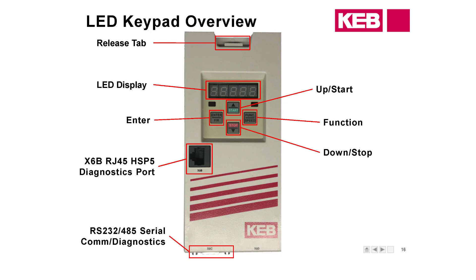The keypad screen itself has an LED display — that's where your parameter name and parameter number are going to show up. We have Enter, Start, Stop, and Function buttons for viewing and changing parameters, and then the release tab at the top. The release tab must always snap up in order for the keypad to be properly seated; if it's not properly seated, we could have intermittent communication errors.